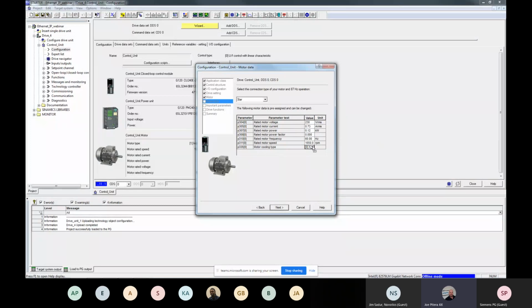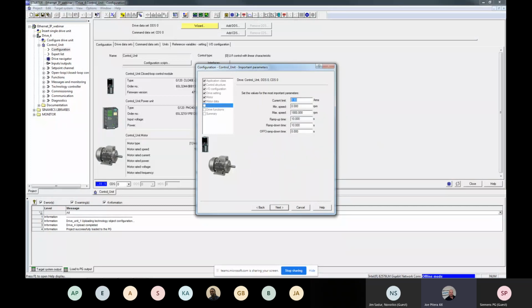And we have the cooling type is naturally ventilated. Over here you could have forced cooling if you had an external fan. If it was liquid cooling by some external liquid cooling, or if there is a totally enclosed non-ventilated type motor, you would pick the final one there in the selection.